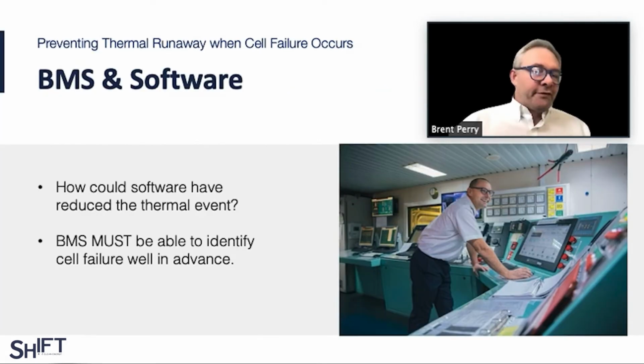When you look at the other side of it, it is the software. So could software prevent thermal runaway? No. Can software predict thermal runaway? Yes. So your battery management system has to be designed to effectively manage the fire before it can occur, and you have to have the risk protocols built into the operation of the system to ensure that the alarms and the operating conditions and the training are driven towards making sure that we proactively manage instead of reactively manage anything that could be a firefighting failure.